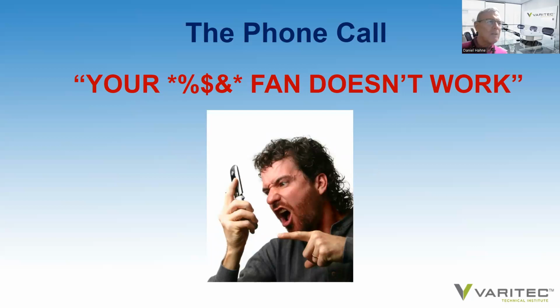I've been at the receiving end of this conversation in the past throughout my rather long career in the industry, being approached by a contractor to say that the fan doesn't work. Well, if a fan is short of airflow, I can assure you 90 to 95% of the time, if not more, it's not the result of the fan unless there's a faulty motor, a faulty VFD, or whatever.